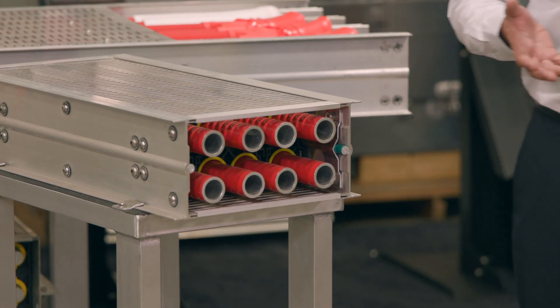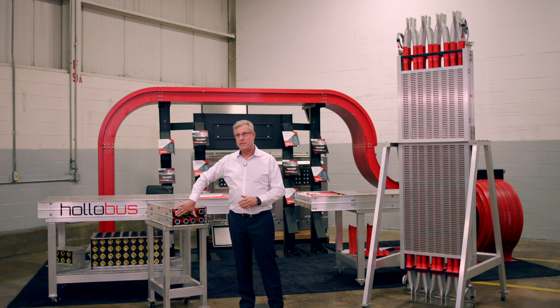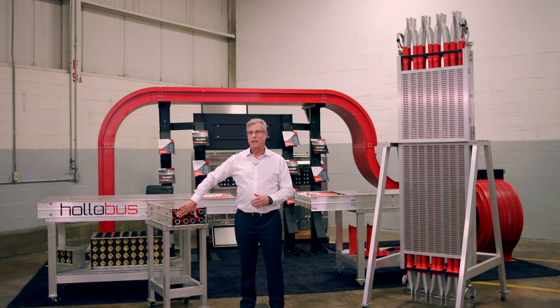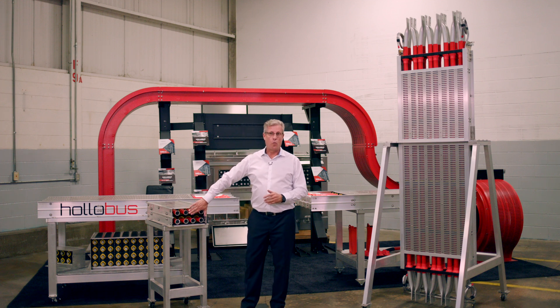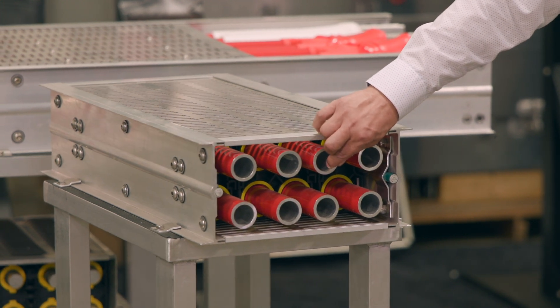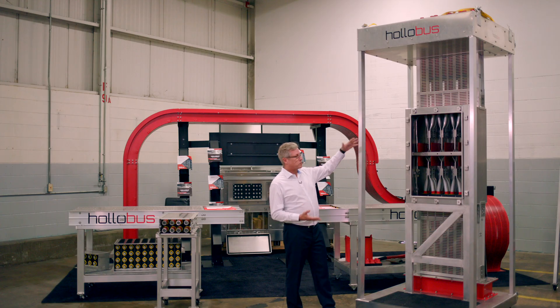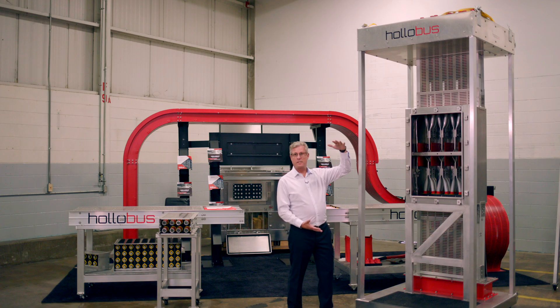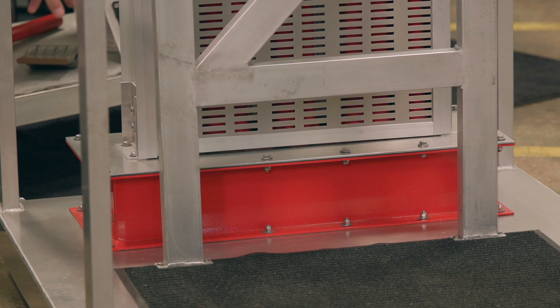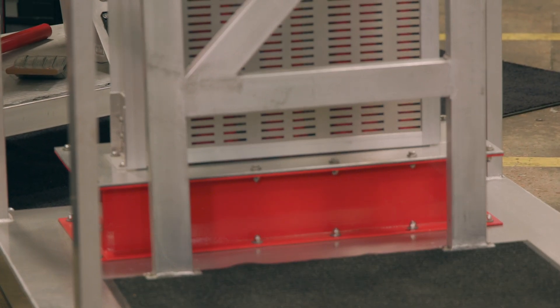Hollobus is not just a name — it's actually the system itself. You'll see here that it's hollow; this is the conductor itself. This is why it's such a large labor savings, and also why it's so efficient. The sizing and thickness of the walls are custom designed to get the most efficiency out of this product and material. This system can shrink and expand two inches on every floor — no other feeder in the world does that. Inside that water dam is an environmental seal to stop water from passing floor to floor, and also a two to four hour fire stop.